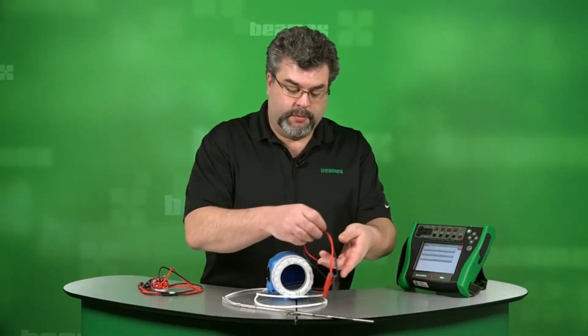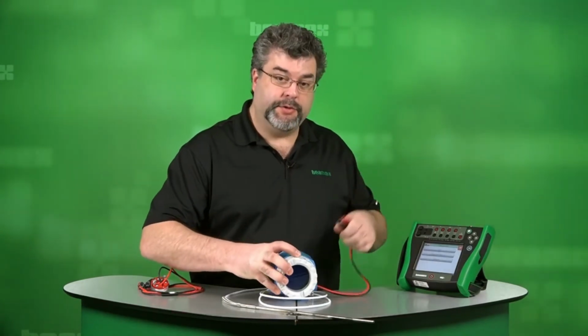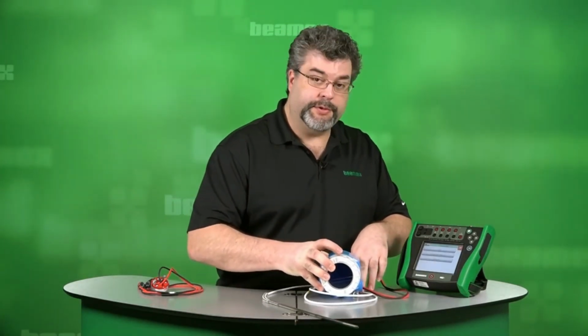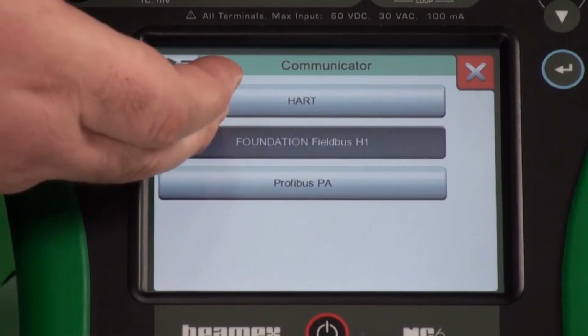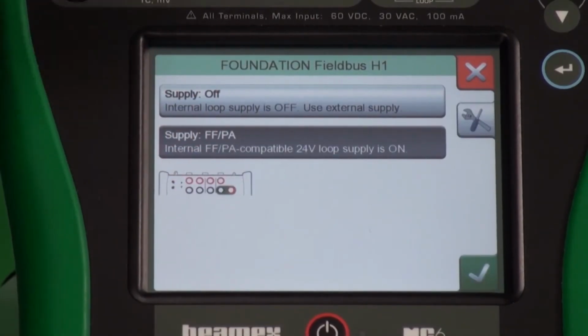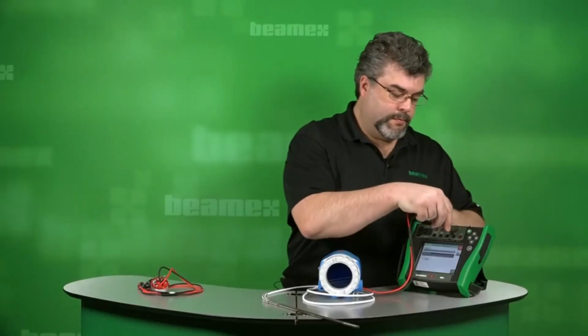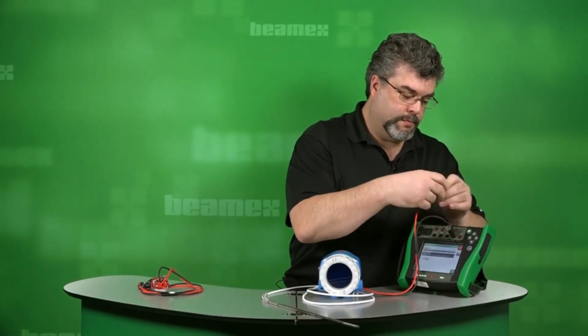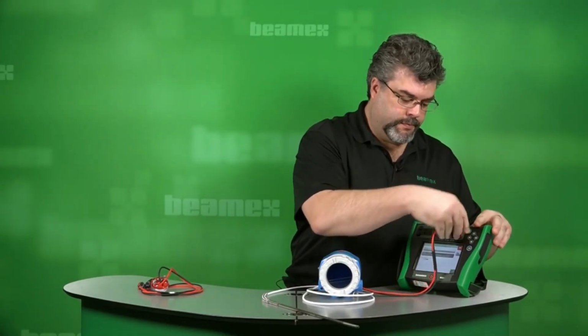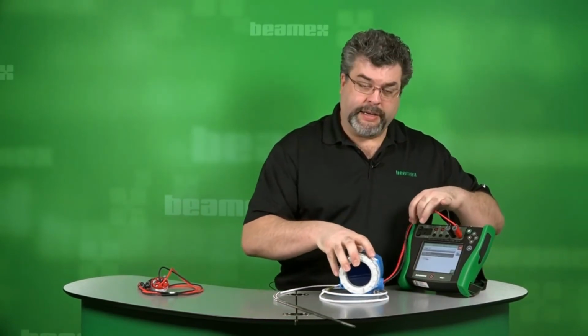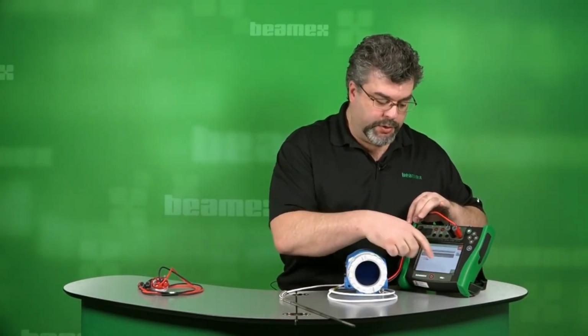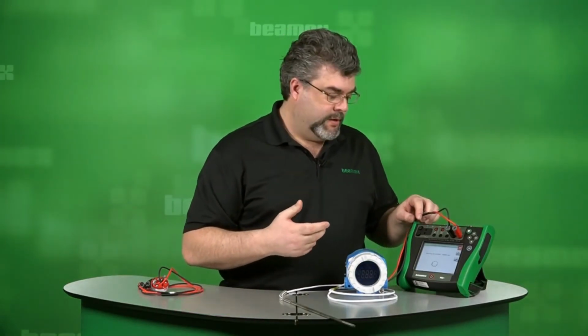Let me make a few connections. Let's connect the Foundation Fieldbus device to the communicator. We have an RTD sensor connected to this Foundation Fieldbus temperature transmitter. Foundation Fieldbus, now we follow the wiring diagram. If we were not going to provide loop power, we'd pick the top one, but we do want loop power as well as the 50 ohm resistor that's built in.